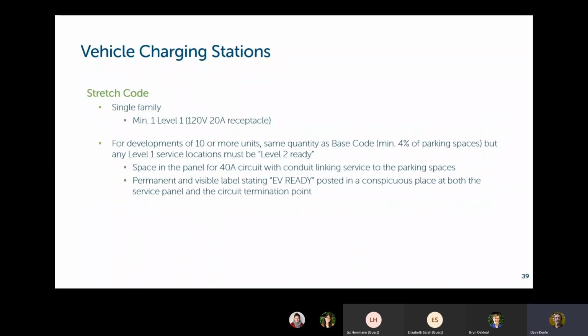For the stretch code, for single family, you need one level 1 charger. So basically, that's a standard household current outlet within reach of where you're going to park the car. For developments of 10 or more units, it's the same as the base code, but any level 1 service locations must be level 2 ready. So that means that back at the panel box and the cabling must be sufficient to carry 240 volts. And you need signage indicating where those EV-ready spaces are.